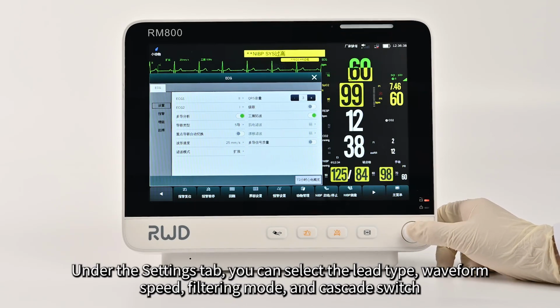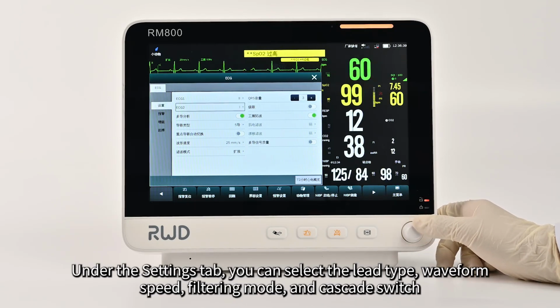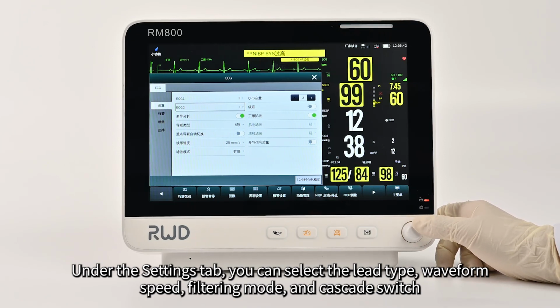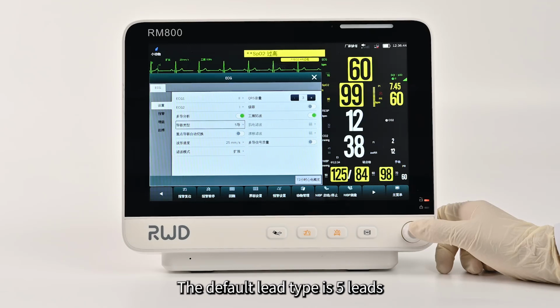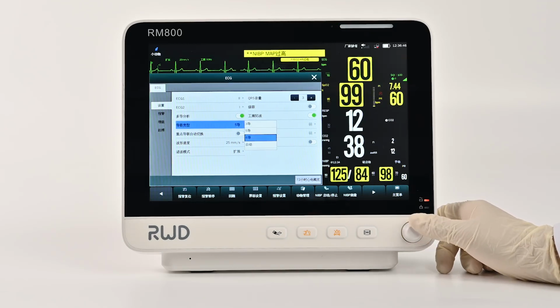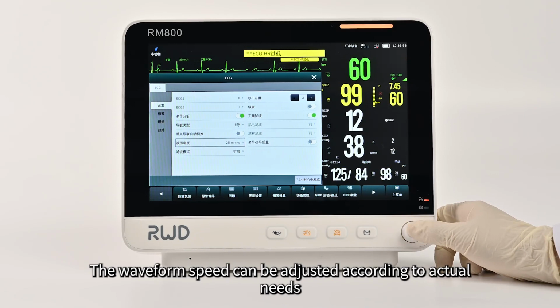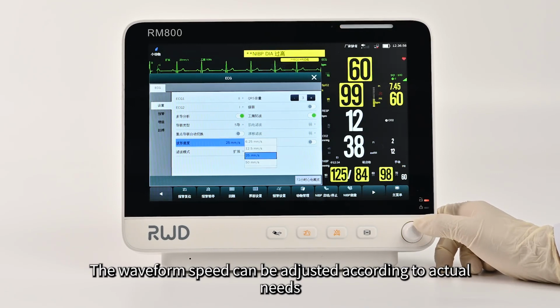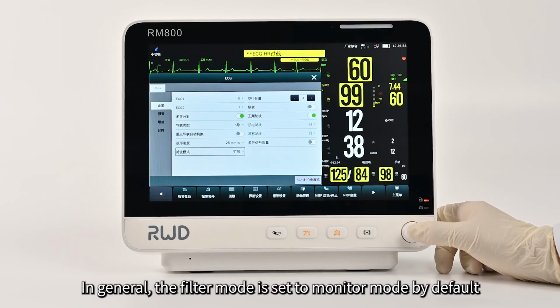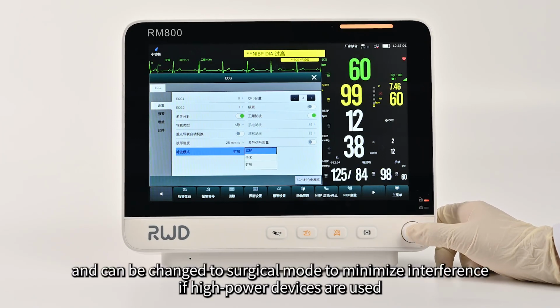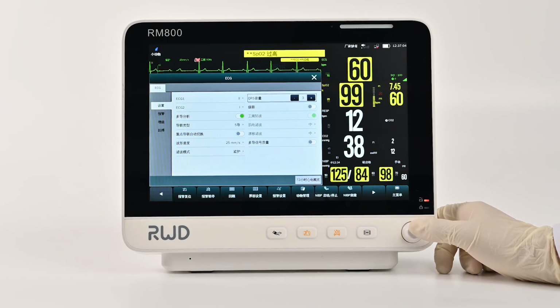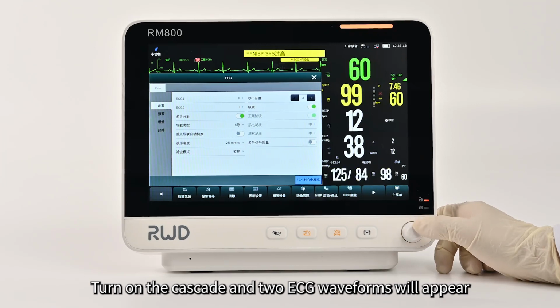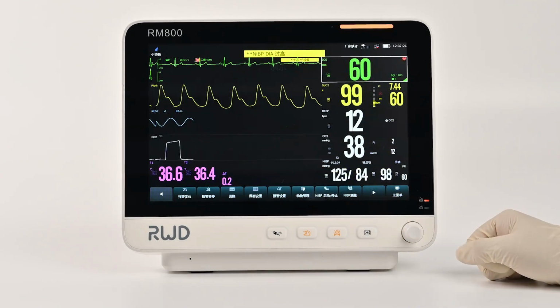interface. Under the Settings tab, you can select the lead type, waveform speed, filtering mode, and cascade switch. The default lead type is 5 leads. The waveform speed can be adjusted according to actual needs. In general, the filter mode is set to monitor mode by default, and can be changed to surgical mode to minimize interference when high-power devices are used.